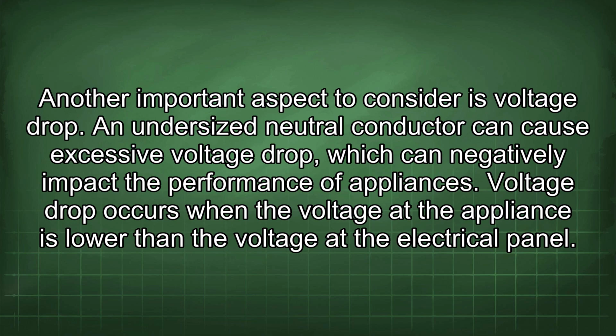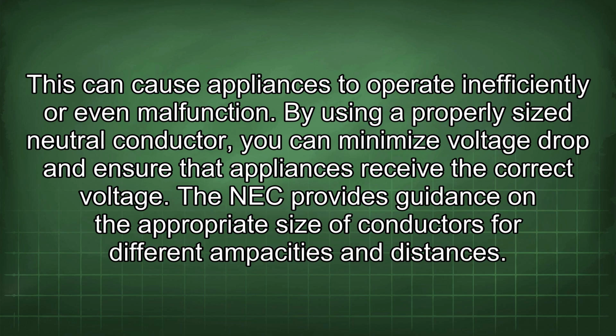An undersized neutral conductor can cause excessive voltage drop, which can negatively impact the performance of appliances. Voltage drop occurs when the voltage of the appliance is lower than the voltage at the electrical panel. This can cause appliances to operate inefficiently or even malfunction. By using a properly sized neutral conductor, you can minimize voltage drop and ensure that appliances receive the correct voltage.